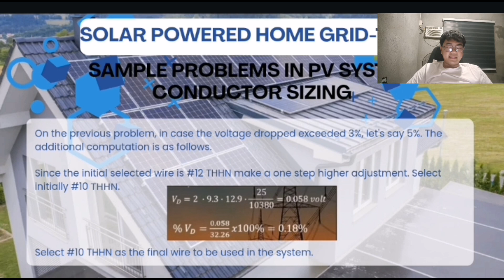Ang K-direct current constant ay isang fixed value na ginagamit para kumatawan sa resistance ng conductor na may sukat na 1,000 circular mils at 1,000 feet ang haba. Sa temperature na 75 degrees Celsius, ginagamit ito para mas mapadali ang pagko-compute ng resistance at voltage drop sa mga electrical conductors. Magkaiba ang value nito depende sa materials. Sa copper, ang K value ay 12.9 ohms, habang sa aluminum naman ay 21.2 ohms. Dahil mas mataas ang resistance ng aluminum kumpara sa copper.